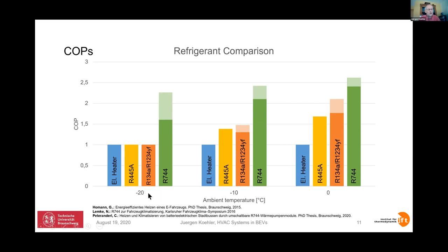However, what you can see at very low temperatures, minus 20, is that 1234YF and all the mixtures are not really well suited for the heat pump mode. They just have a COP of 1, meaning the energy which goes into the system goes also out of the system, but nothing is gained from the environment, as is the case for the electric resistance heater. CO2, with its high operating pressure, has an advantage here, and we can really gain something from the environment, and we reach a COP between 1.5 and 2, more or less.